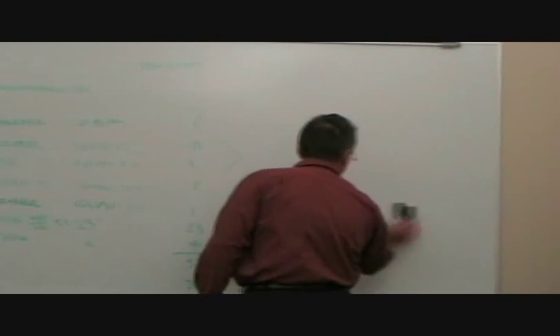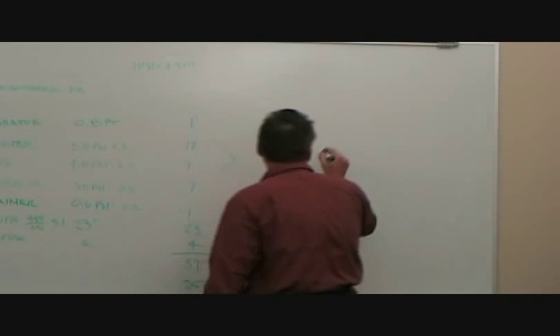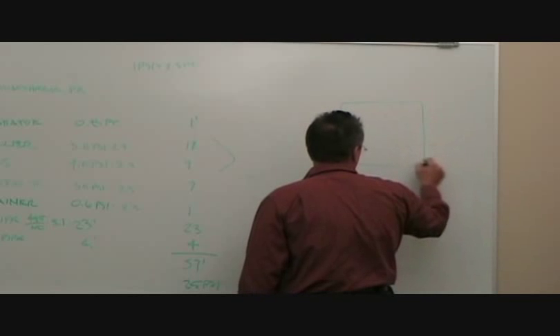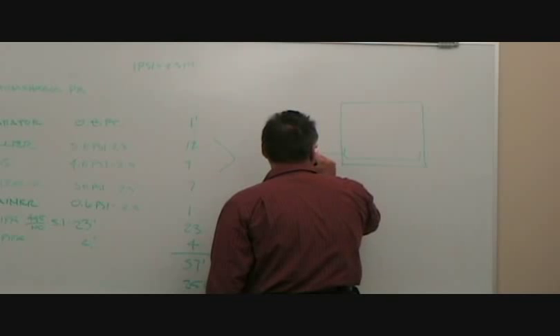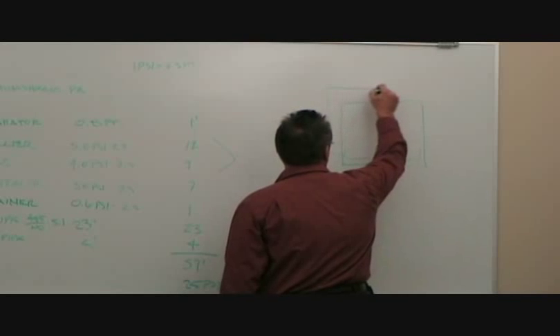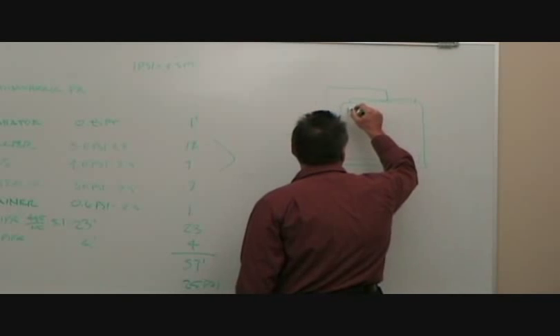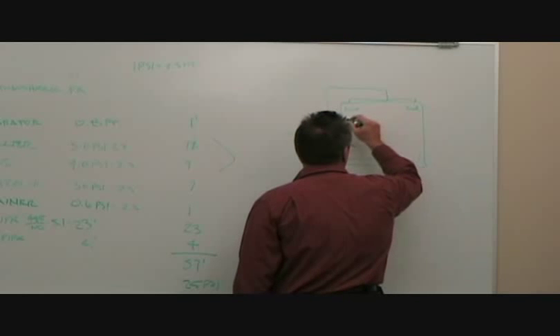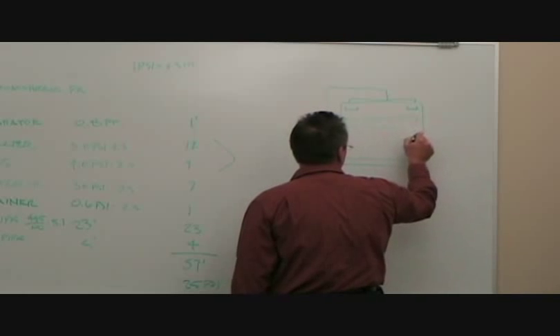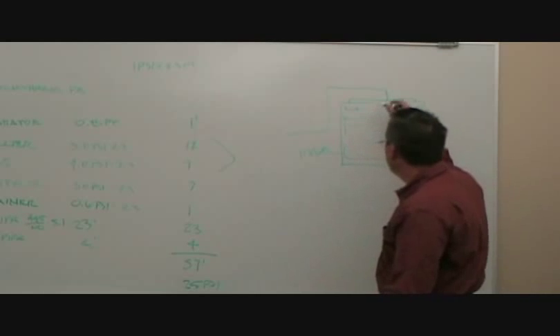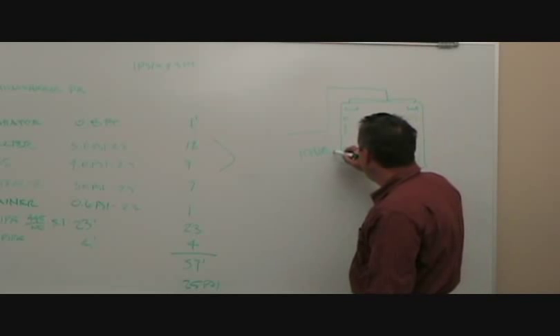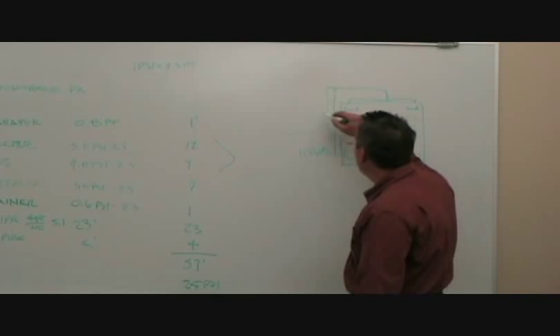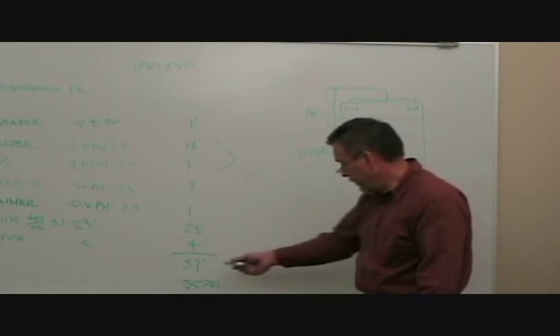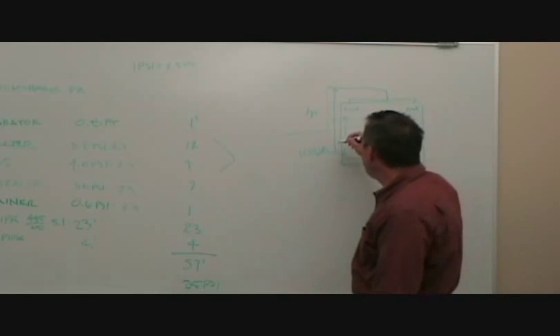So what's different right here at the cooling tower? I've got similar flows, similar type fittings, similar chiller barrel, so it's going to have a very similar calculation. But now I got this cooling tower sitting out here. There's my pump. There's my return line coming out here, usually connecting something like that right there, going down through the internal basins, hot water distribution, across the fill, or the drift eliminators, down through the fill, eventually dripping down to the basin. Well, this is open, right? So now I've got to compensate for lifting that pipe up. There's H, that right there. So when I calculate my pressure loss through my pipe and fittings, this is an actual lift.